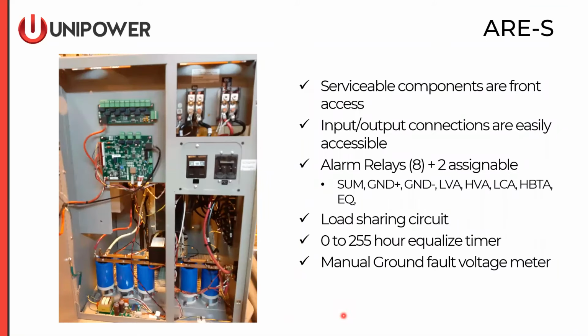Here we have the open door on an ARE-S charger, again showing the interface boards. There's 2 of them this time. The top board is optional. This is how we extend the standard alarm relays. We see the relays, 3 of them on the top of the standard interface board. And then we extend the standards, again, which are high voltage shutdown, AC fail, and rectifier fail relays, to include discrete alarm relay outputs for all other available alarms, including the summary alarm.